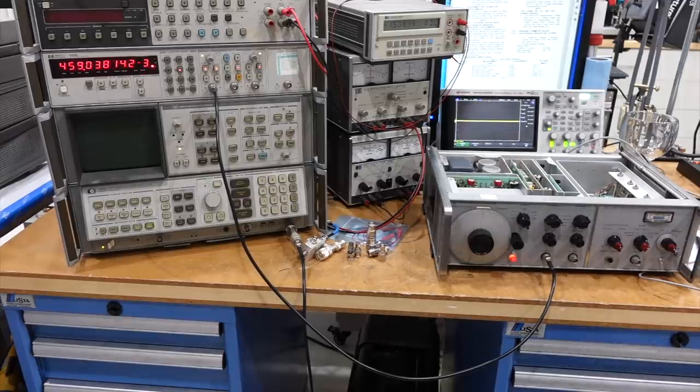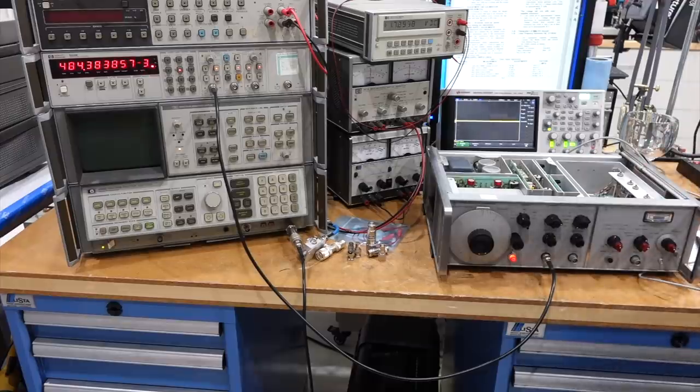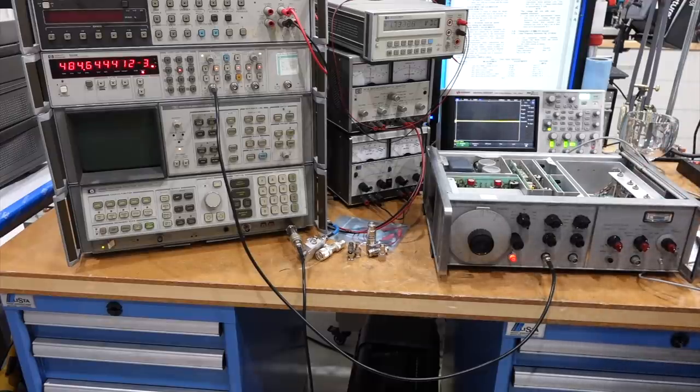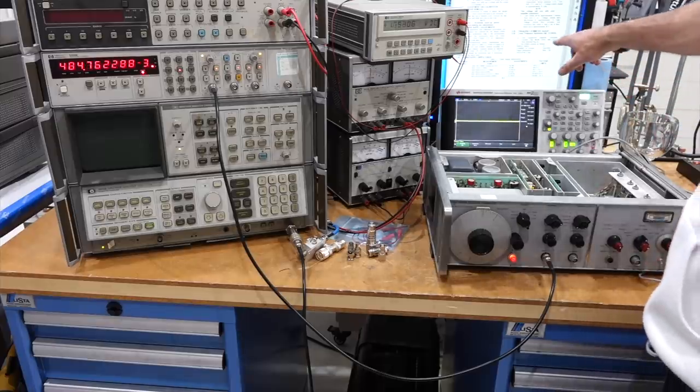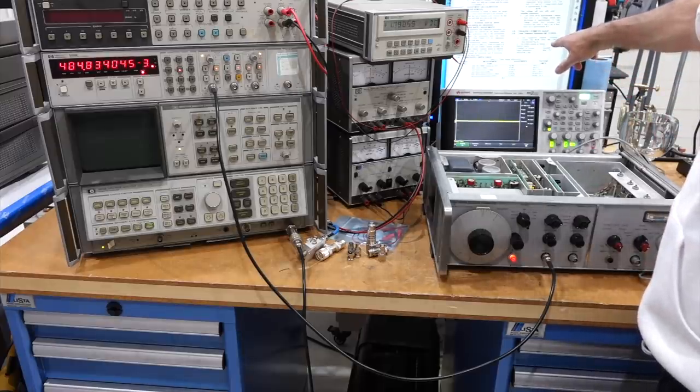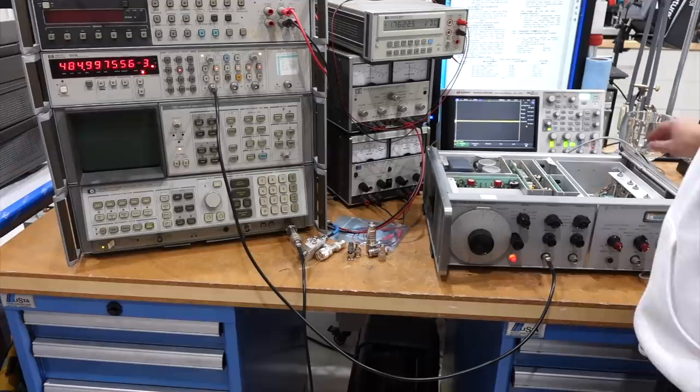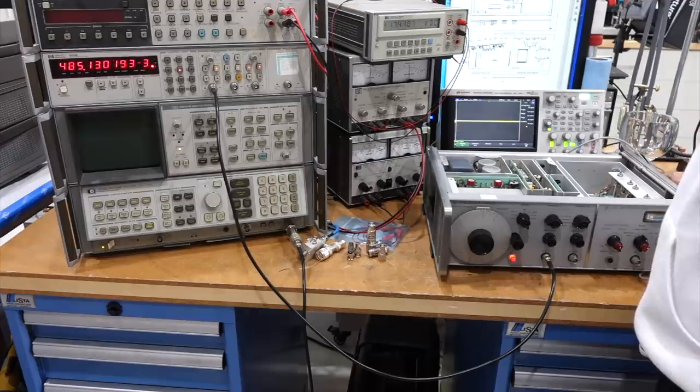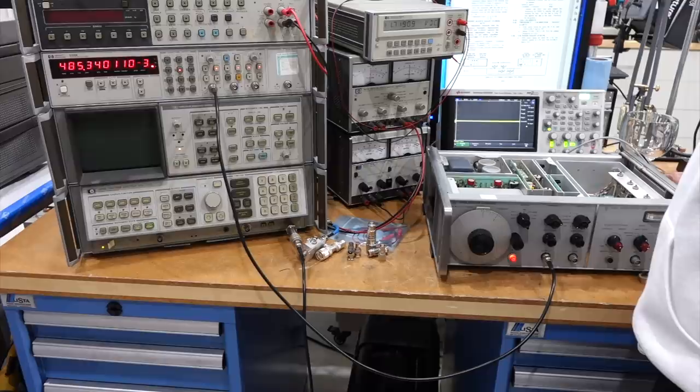So my two current sources are out of balance, and I don't have enough range to bring them back in balance. Aha! And that's exactly what you don't want to happen. I can't get the symmetry into adjustment, not even close. The manual says that you can change some factory preselected resistors if that happens. But this seems so far out of whack that I am thinking something more serious is wrong with the instrument.